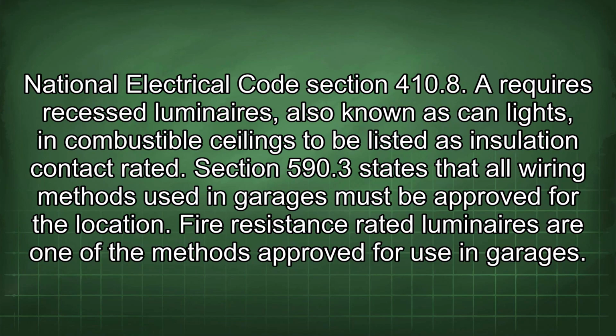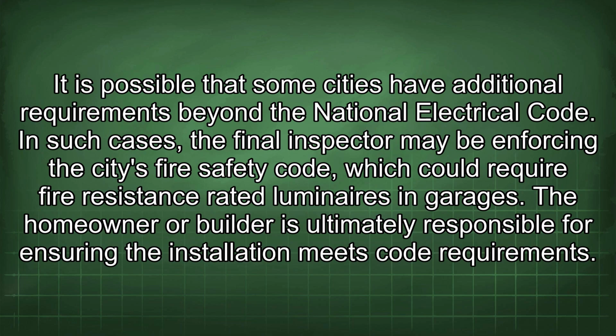National Electrical Code Section 410.8 requires recessed luminaires, also known as can lights, in combustible ceilings to be listed as insulation contact rated. Section 590.3 states that all wiring methods used in garages must be approved for the location. Fire resistance rated luminaires are one of the methods approved for use in garages. It is possible that some cities have additional requirements beyond the National Electrical Code.